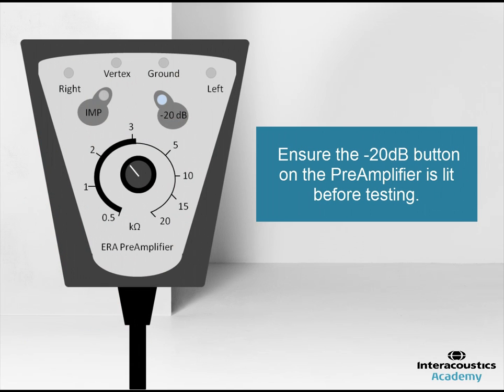Lastly, the gain is reduced minus 20dB for the preamplifier in order to handle the muscle potential of the response.